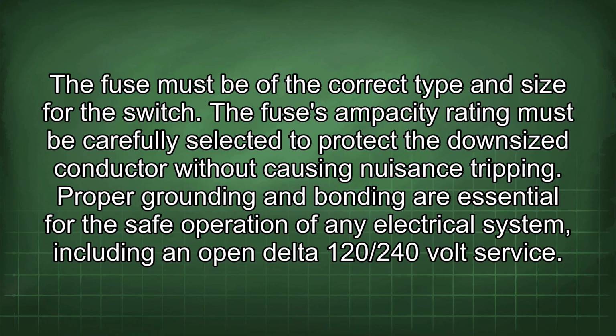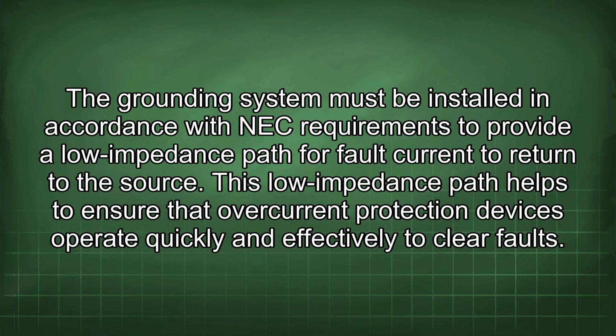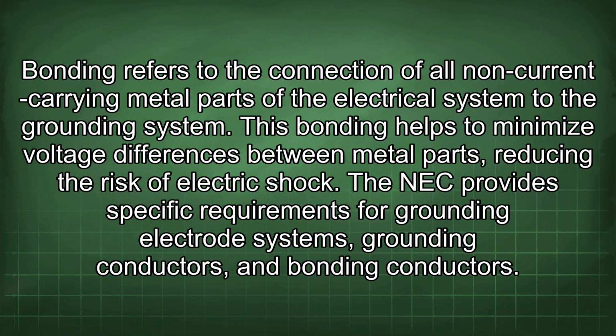Proper grounding and bonding are essential for the safe operation of any electrical system, including an open delta 120/240 volt service. The grounding system must be installed in accordance with NEC requirements to provide a low impedance path for fault current to return to the source. This low impedance path helps to ensure that overcurrent protection devices operate quickly and effectively to clear faults. Bonding refers to the connection of all non-current carrying metal parts of the electrical system to the grounding system. This bonding helps to minimize voltage differences between metal parts, reducing the risk of electric shock.